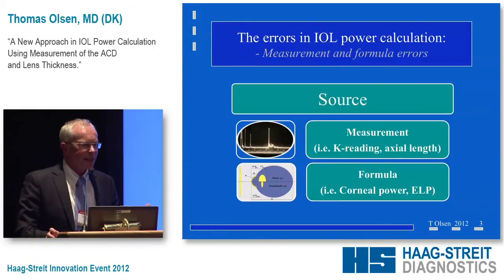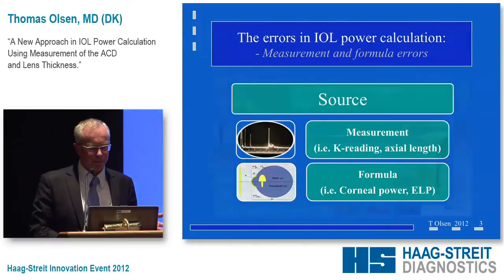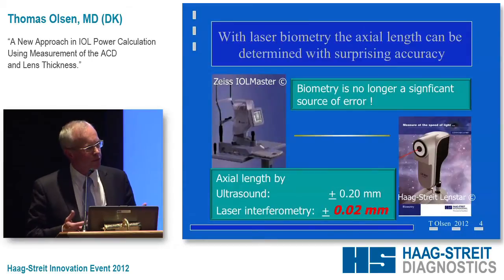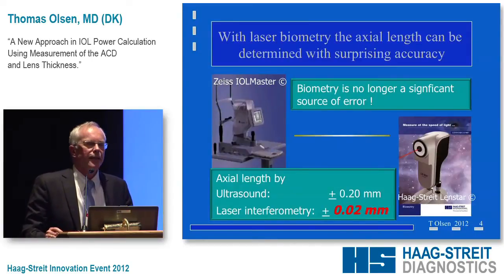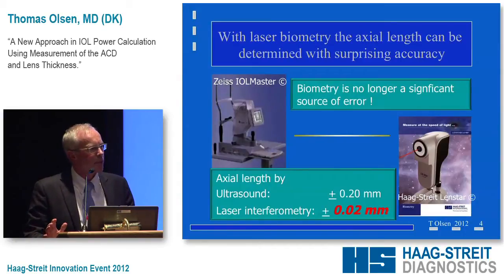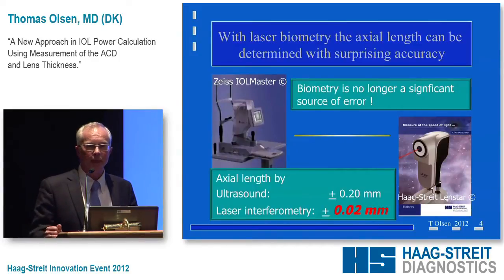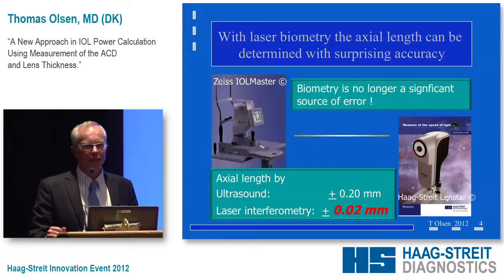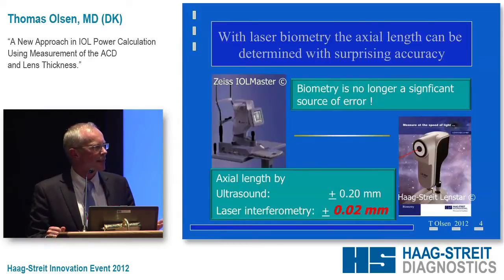We have the measurement errors and we have the formula errors. Since the introduction of laser biometry — the IOL Master came around 2000 — we had a new scene. The accuracy with laser biometry is so incredibly high that a standard deviation of about 20 microns on the axial length will translate into less than a tenth of a diopter error at the spectacle plane. But in my practice, not every patient ends up within a tenth of a diopter, so we must have more errors in the game.